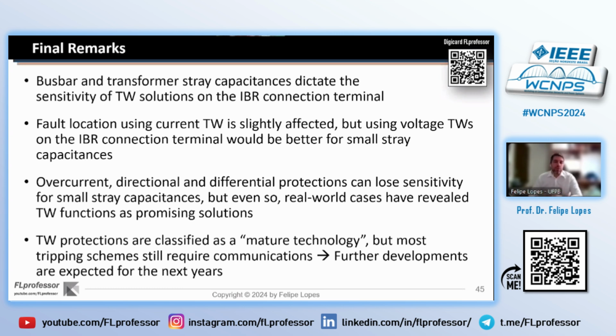Most of the solutions still require communications to implement tripping schemes. And I believe that in the next coming years, the functions will probably evolve toward allowing non-unit protections in this type of system and being even more independent from other auxiliary functions that are usually applied to guarantee the reliability and security of traveling wave protections.